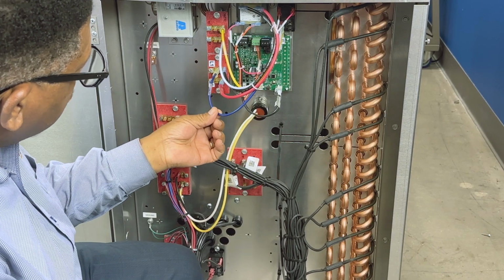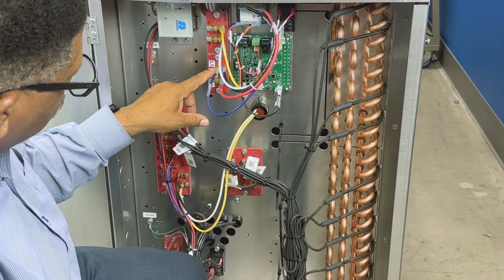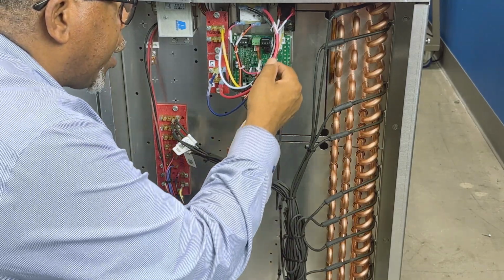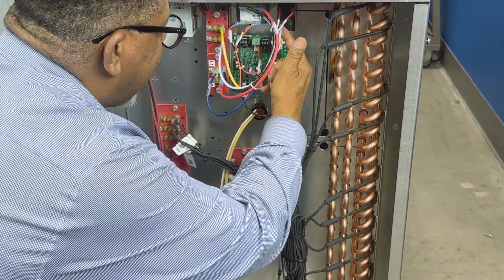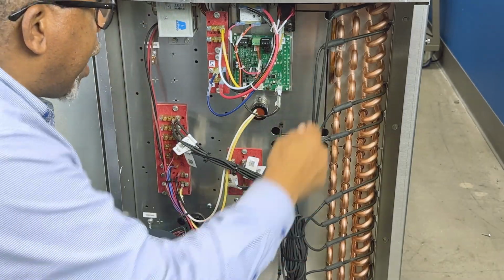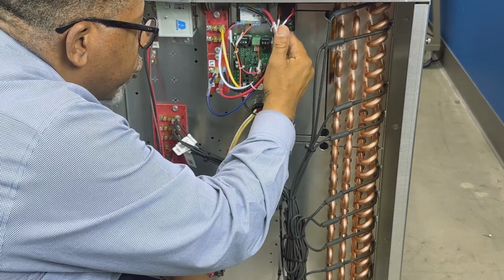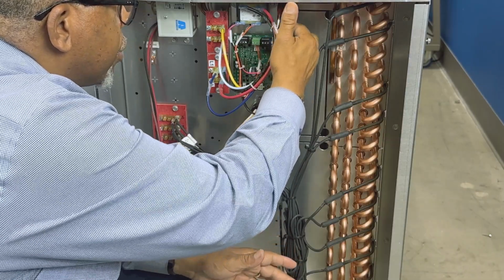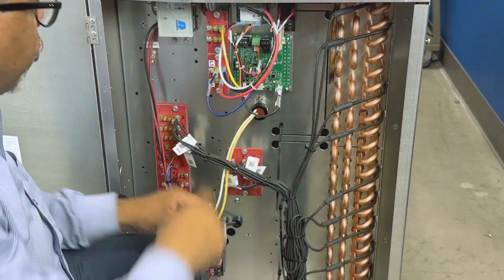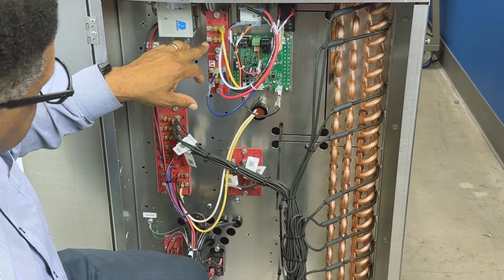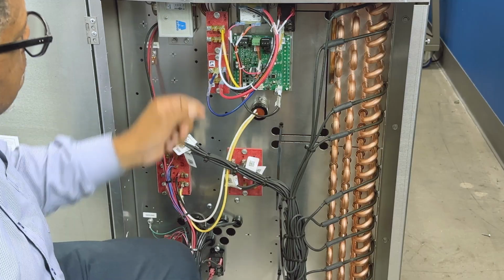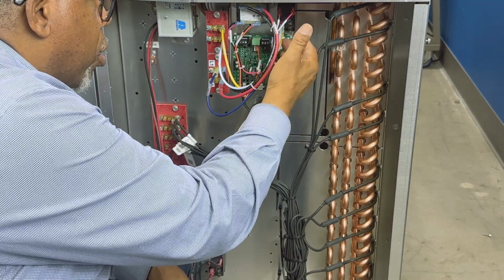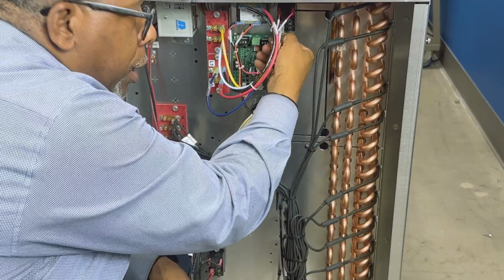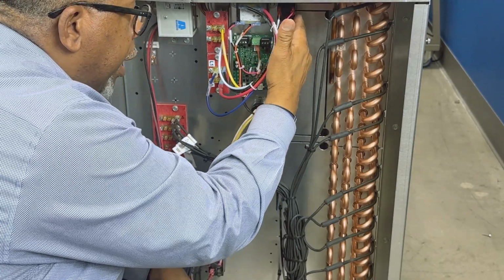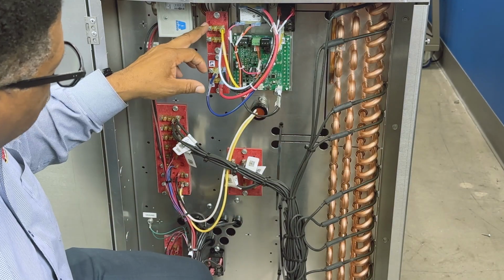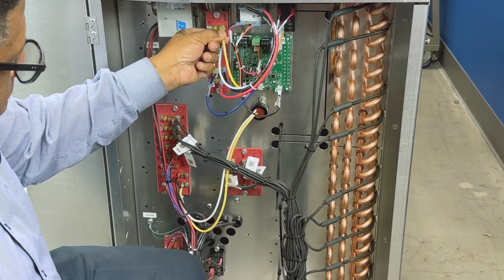You've got your dark blue wire, which lands on L1, but also on the relay here in the middle position on the left-hand side. Also on the relay, we have a light blue wire at the top position of those three positions, left-hand side of the relay, takes the light blue, and that goes all the way over to the terminal strip at T2, light blue. Finally, we've got our yellow wire that plugs into the last end, the bottom end there on the relay, all the way over to T1 on the terminal strip.